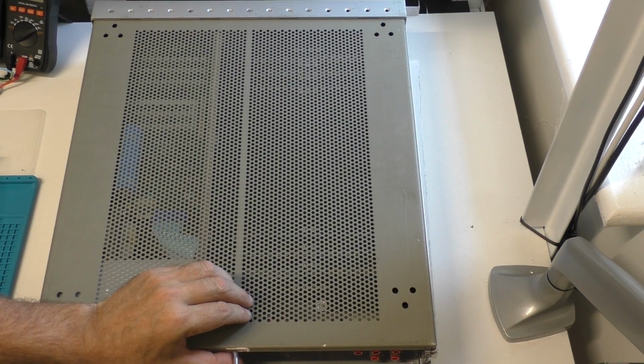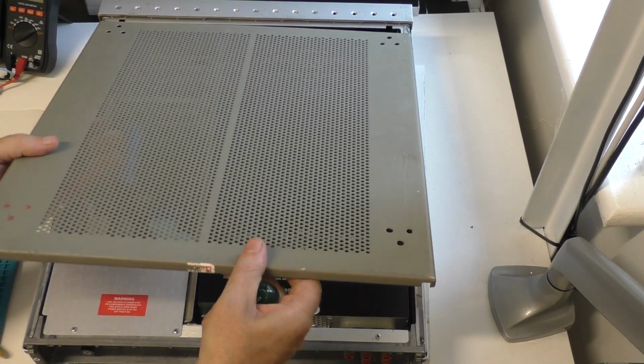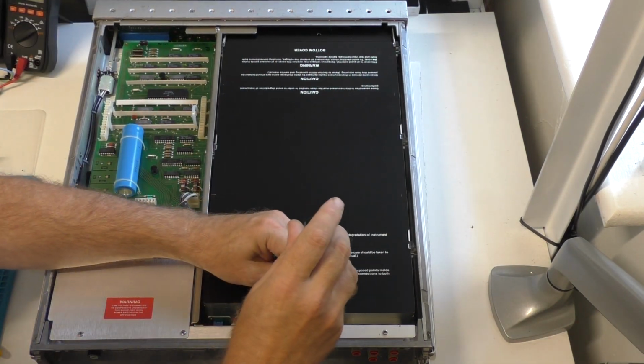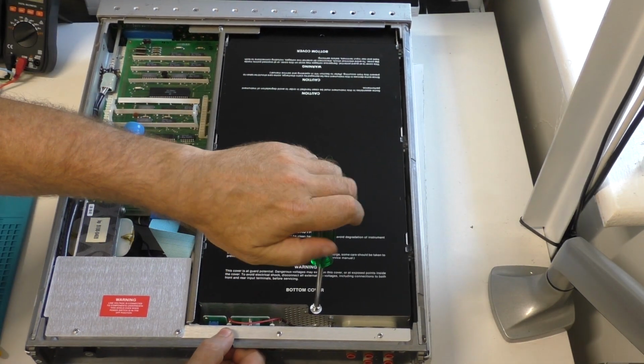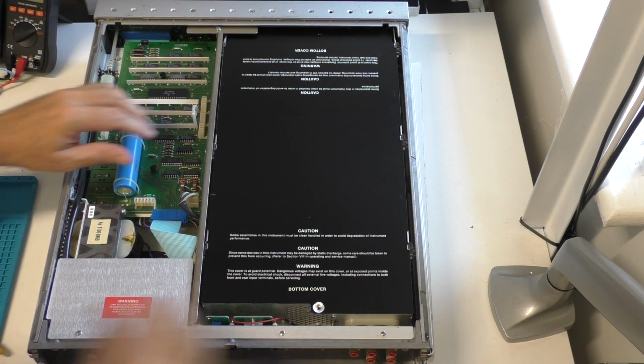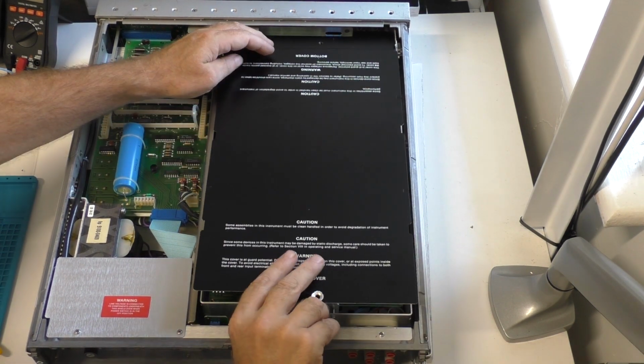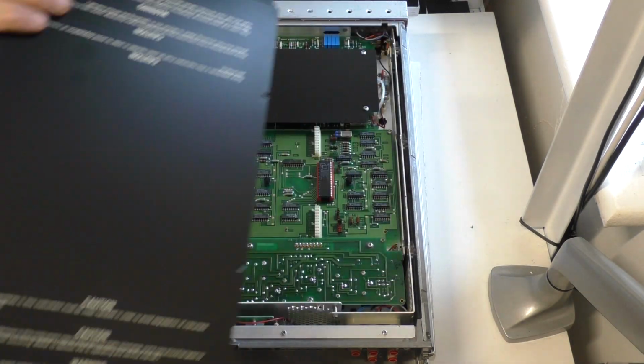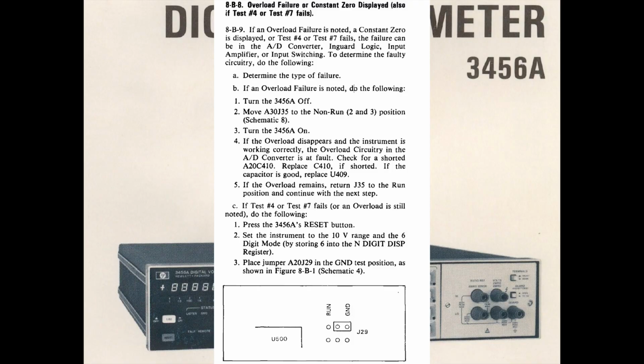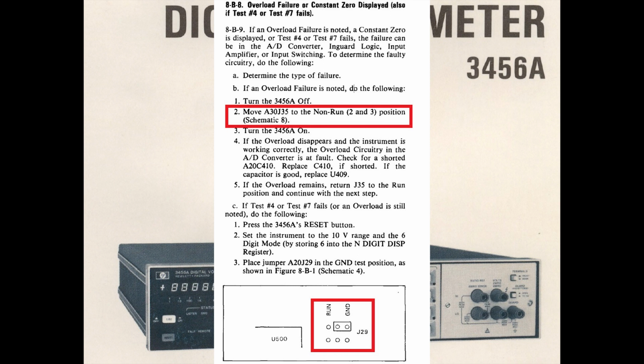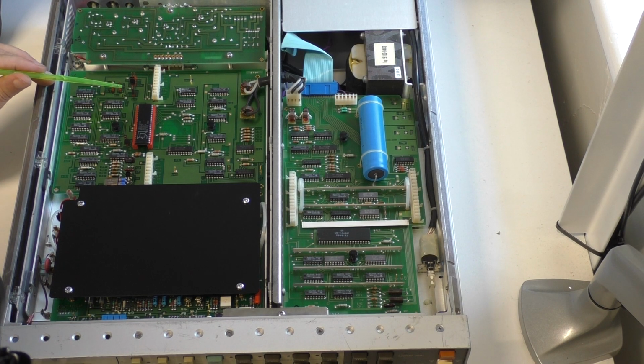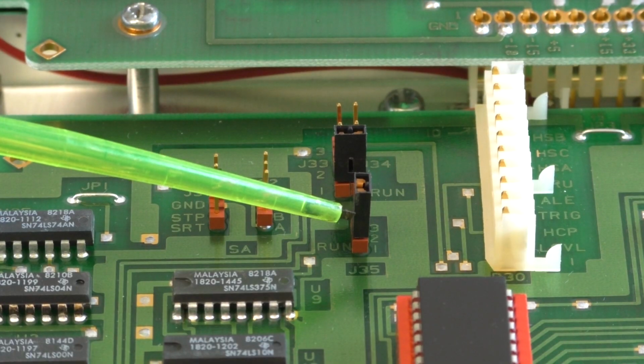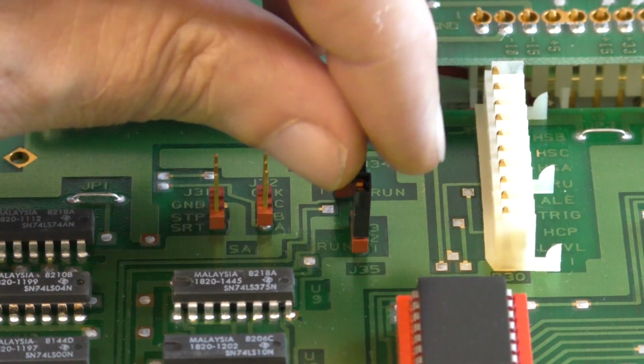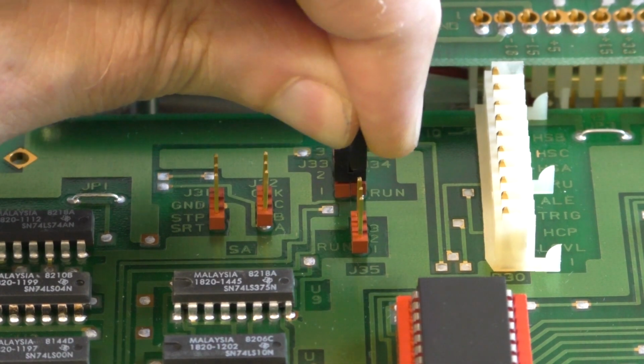Unscrew the bottom cover. Remove and set aside. Unscrew the internal bottom cover. Remove and set aside. Let's refer back to 8B8.2 of the service manual. We need to change J35 jumper on the A30 board. The A30 board is on the bottom of the machine. The jumper is in the run position on pins 1 and 2. Let's change jumper to pins 2 and 3.